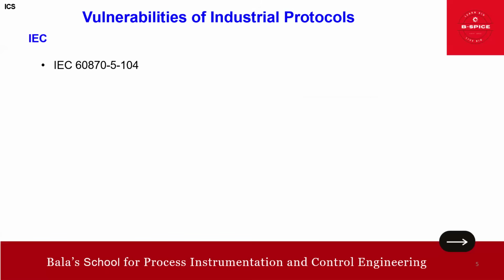Let us start with IEC 60870 part 5-104. This is an unencrypted protocol, meaning it transmits data in plain text without any authentication mechanism over TCP/IP. That is the challenge here. IEC 60870-5-104 is an international standard providing communication between SCADA and substation. Just remember: 60870, SCADA and substation. In transmission, the application layer of this protocol conveys an application service data unit, called ASDU.